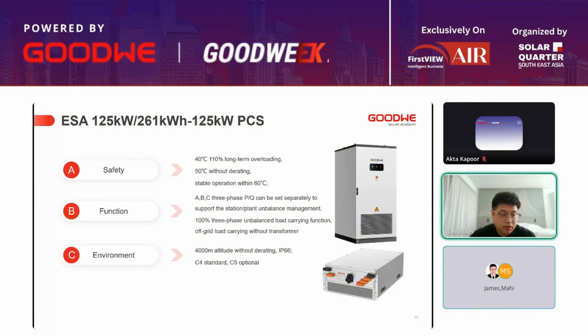We introduce this high capacity energy storage system designed for C&I applications. Key features include high temperature tolerance, with stable operation within 60 degrees. Using 110% overload, the long time overloading capacity can be controlled normally within 40 degrees.